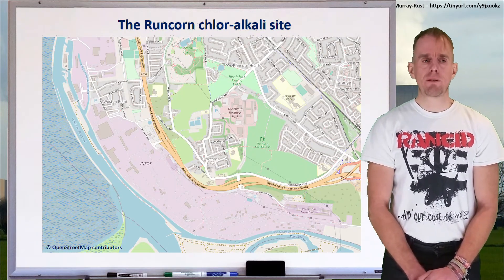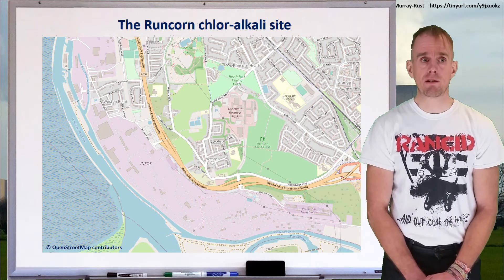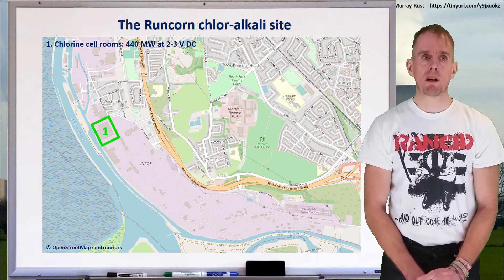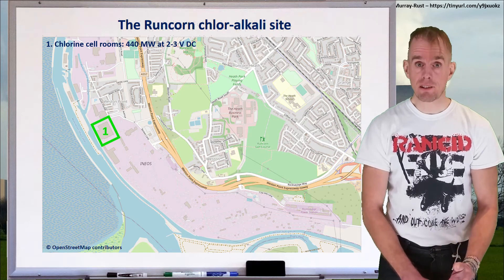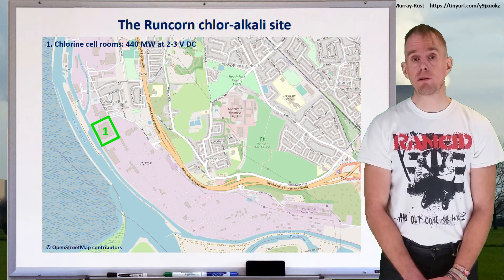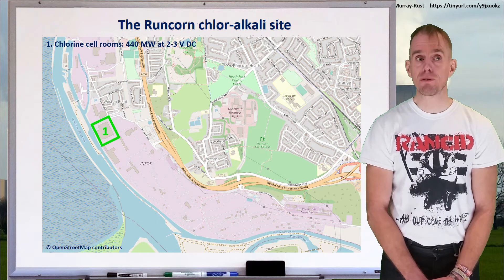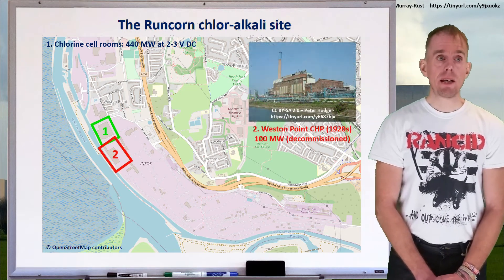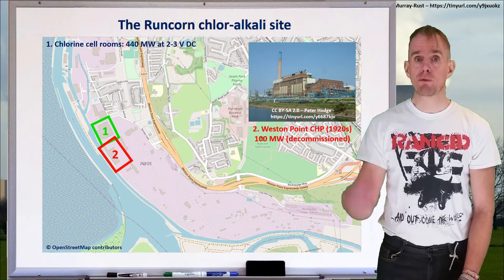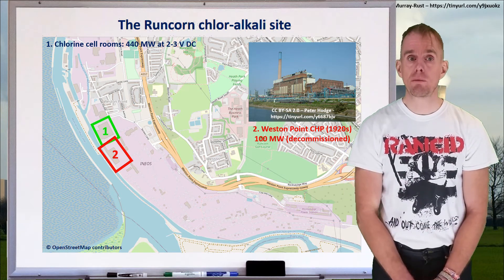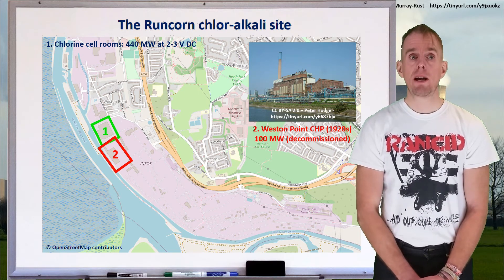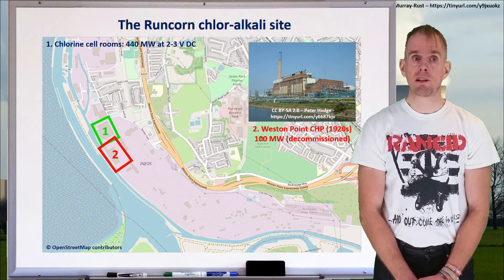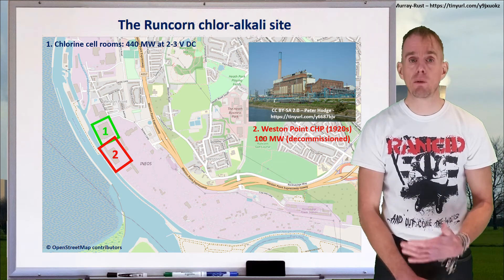The chlorine cell rooms at the northern end of the site require about 440 megawatts, running off DC at around two to three volts — corresponding to many thousands of amps. Right next door, the old Weston Point power station was commissioned in the 1920s as a coal-fired combined heat and power plant supplying both electricity and steam to the site, with a capacity of about 100 megawatts. That power plant has since been decommissioned.